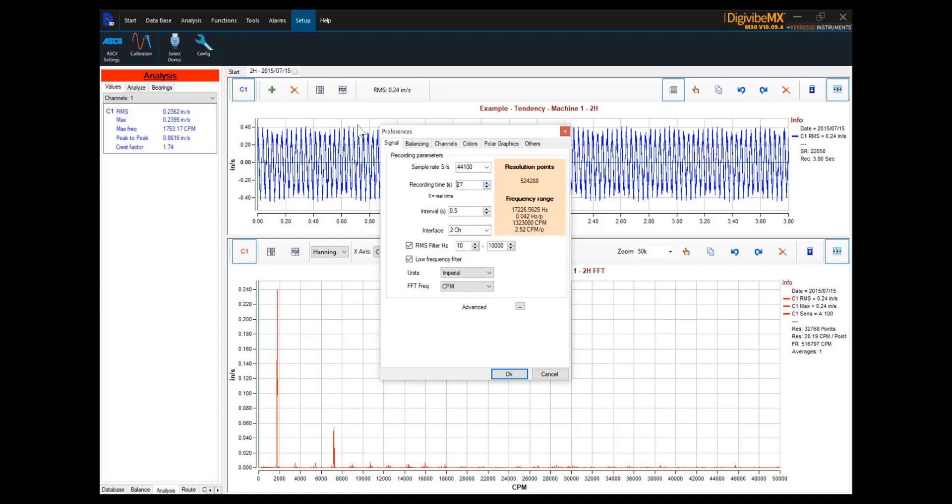So, if we went as far as setting the recording time to 48 seconds, doubling it yet again, we now have just over one cycle per minute represented by each spectral line in the FFT, and a 0.021 hertz range depicted by each point in our FFT spectrum.